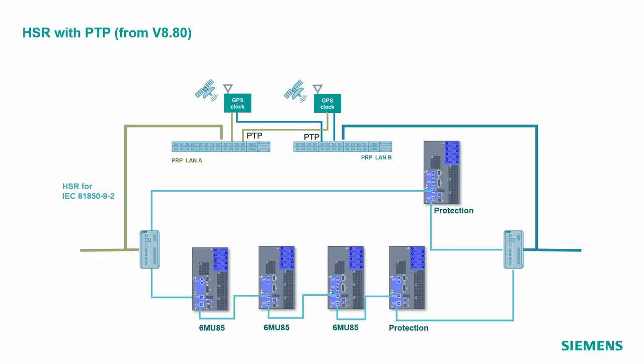Now let's see the example with HSR, but now using the PTP or precision time protocol. What we see here is that we always have our redundant master clocks. We connect them also in a redundant manner from one GPS to the PRP-A and the PRP-B. Those are the backbone switches, and our ring is connected to this backbone to receive the synchronization signal.